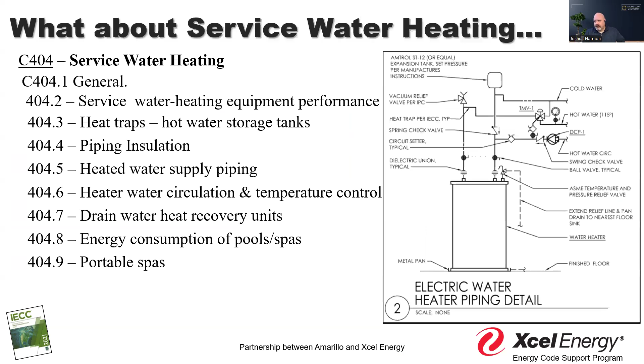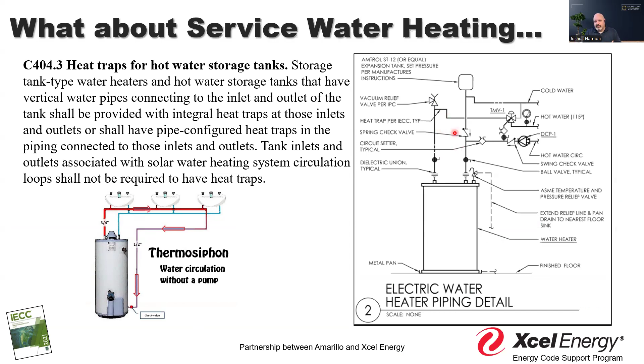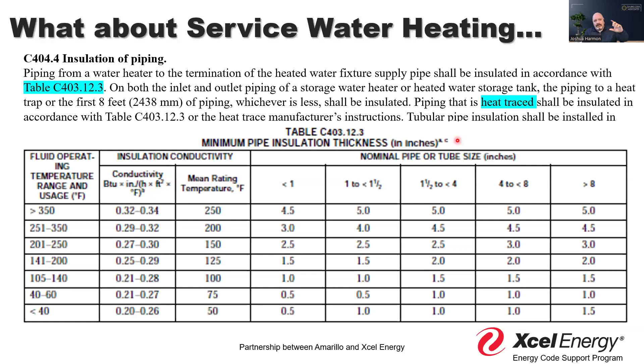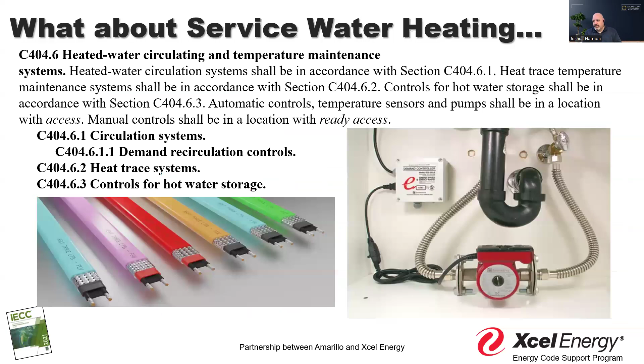So I need to think about that and check my meter, because it may not be designed to handle that flow, potentially creating bigger safety problems for everyone involved. The code addresses not just service water heating systems but also the heat trap concept within expectations, including commercial layouts, and how we protect the pipe: do we insulate, or do we put heat tracing around it? Either way, we maintain the line's temperature to prevent condensation, along with recirculation pumps and similar considerations.